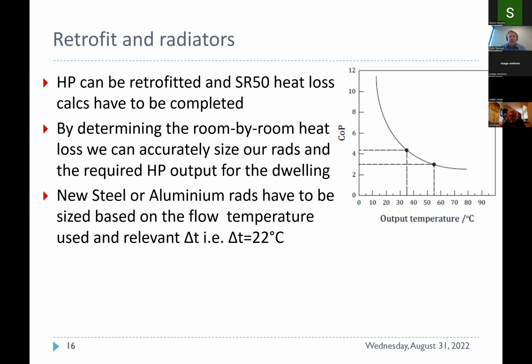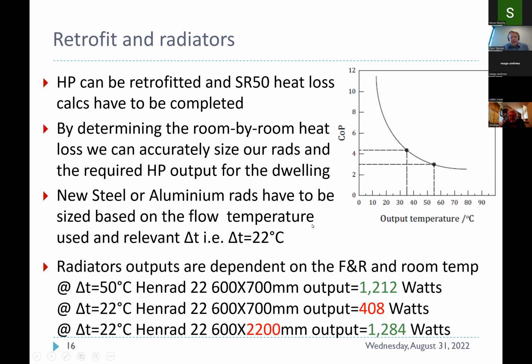In retrofit, more than likely, you'll have to replace your steel or aluminum radiators to ensure that these are meeting the required heat output per room. Just giving you an example here, at a higher delta T, one of our radiators, a double 22, 600 height by 700 wide, will give us roughly 1.2 kilowatts. The same radiator at a delta T of 22 will give us a third of that. And if we want to match the same output, more or less, the radiator is actually over 3 times the size. So it's a 22, 600 by 2.2 meters long.